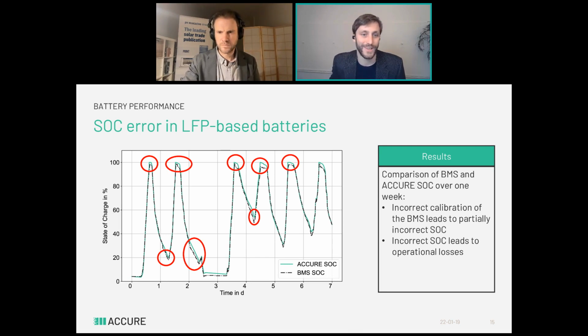I don't know what the error in millivolts is off the top of my head, we can look that up. But again, the ability to calculate in both directions, and also - maybe more interesting in this case - to get the true current out of the measured current, matters, because DC current measurements especially have quite substantial errors. With our methods we've found successful ways of cleaning the current, which automatically leads to better SOC estimations as well.